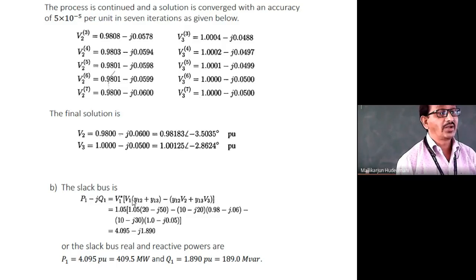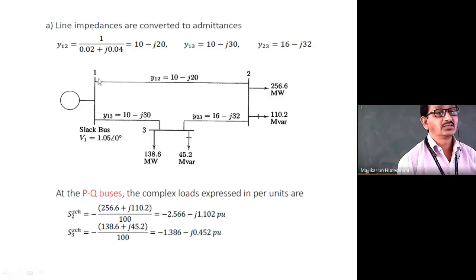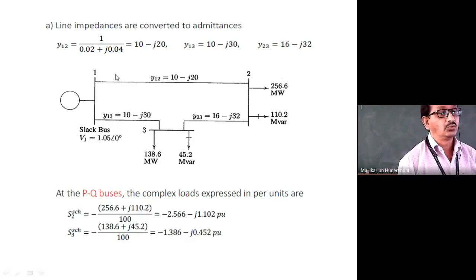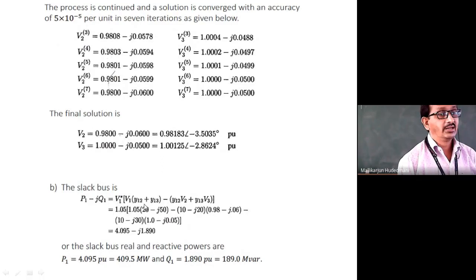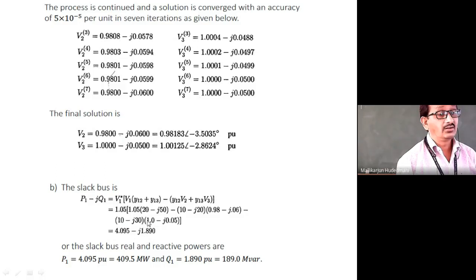The current at bus 1, I1, is I12 + I13, where I12 = (V1 − V2)·Y12 and I13 = (V1 − V3)·Y13. These are the currents flowing along each transmission line. In the expression, the square bracket contains current moving toward bus 2 and current moving toward bus 3, multiplied by V1*. The real term represents active power delivered by the slack bus; the j-operated term represents reactive power. The result is 409.5 MW injected by the slack bus.